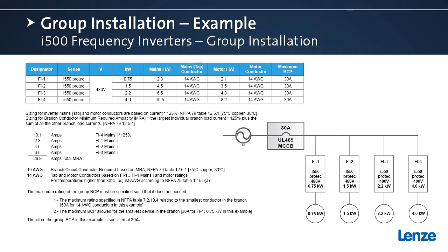sized, we can look at the branch circuit protective device. And here we have two requirements to meet. One is the maximum rating specified in table 7.2.10.4. That table references for the smallest conductor in this circuit, which is a 14 gauge, we can use nothing bigger than a 60 amp branch circuit protective device. There's also a second requirement here that says the maximum branch circuit protective device allowed cannot exceed the rating of the smallest device in the circuit. So that's really what's driving the sizing here.